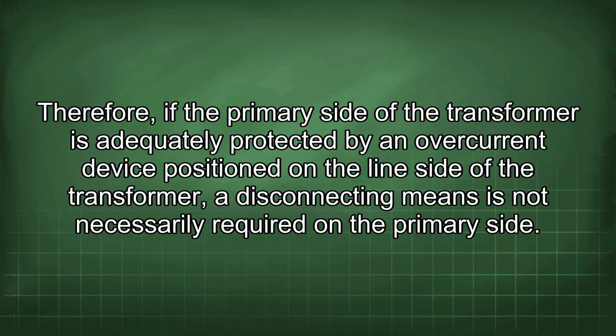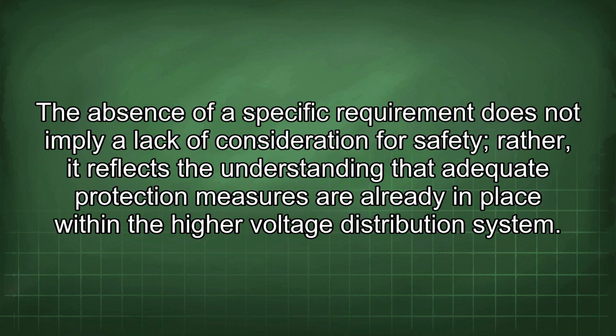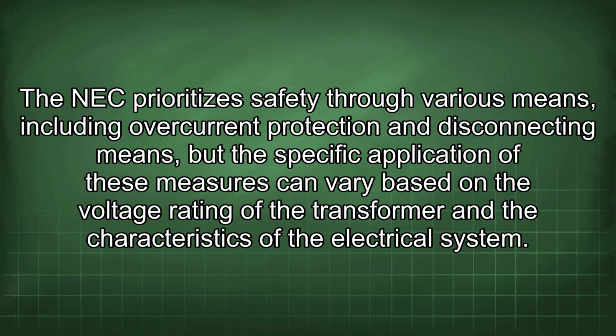Therefore, if the primary side of the transformer is adequately protected by an overcurrent device positioned on the line side of the transformer, a disconnecting means is not necessarily required on the primary side. The absence of a specific requirement does not imply a lack of consideration for safety, rather it reflects the understanding that adequate protection measures are already in place within the higher voltage distribution system. The NEC prioritizes safety through various means, including overcurrent protection and disconnecting means, but the specific application of these measures can vary based on the voltage rating of the transformer and the characteristics of the electrical system.